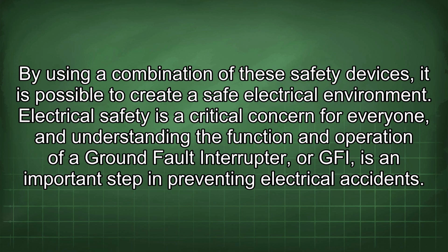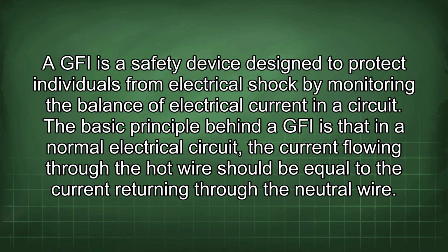Electrical safety is a critical concern for everyone, and understanding the function and operation of a ground fault interrupter, or GFI, is an important step in preventing an electrical accident. A GFI is a safety device designed to protect individuals from electrical shock by monitoring the balance of electrical current in a circuit. The basic principle behind a GFI is that in a normal electrical circuit, the current flowing through the hot wire should be equal to the current returning through the neutral wire.